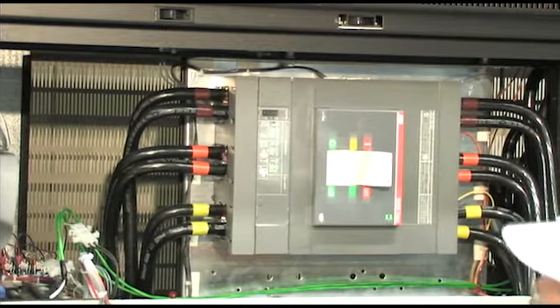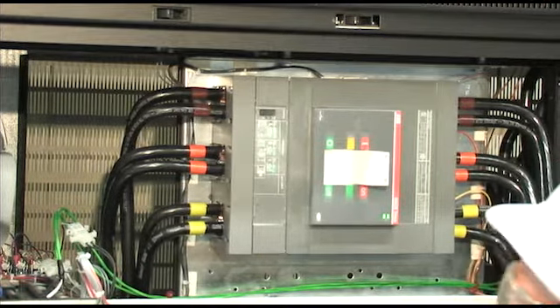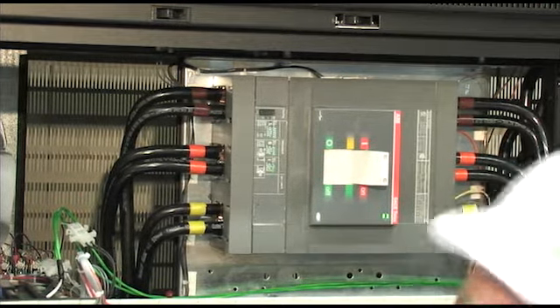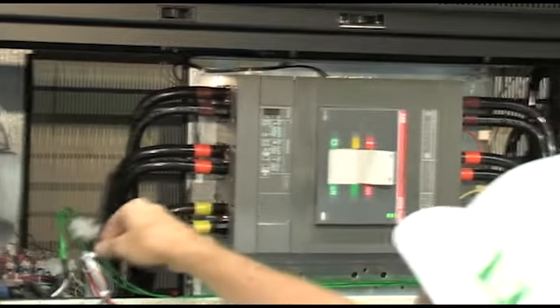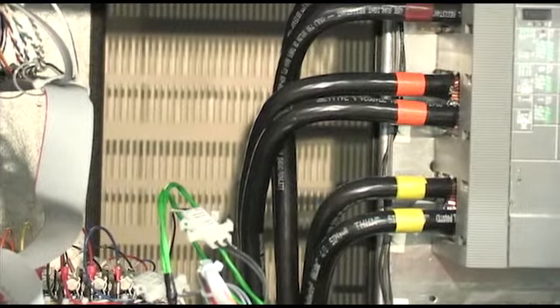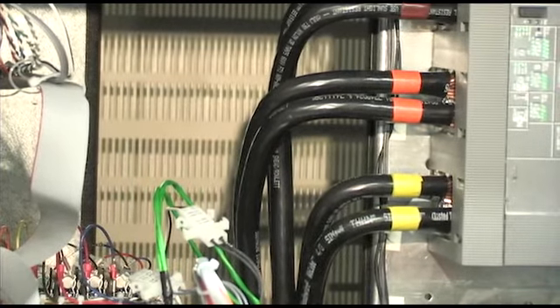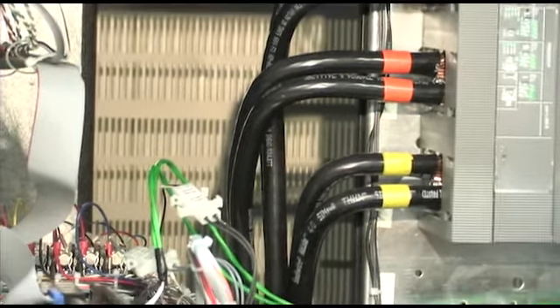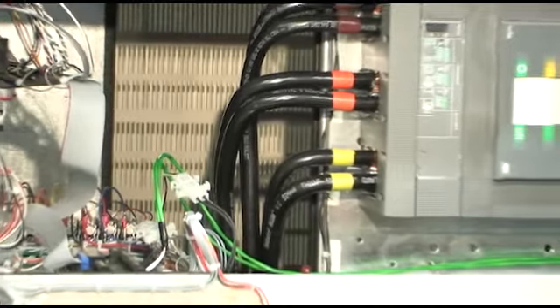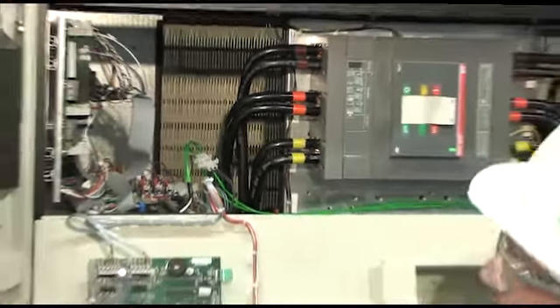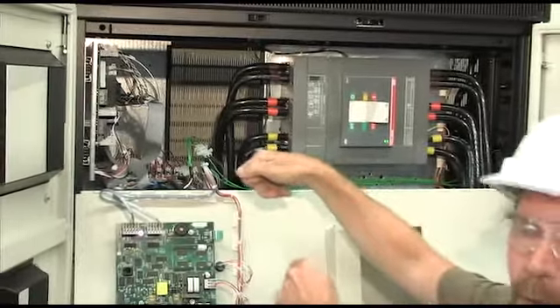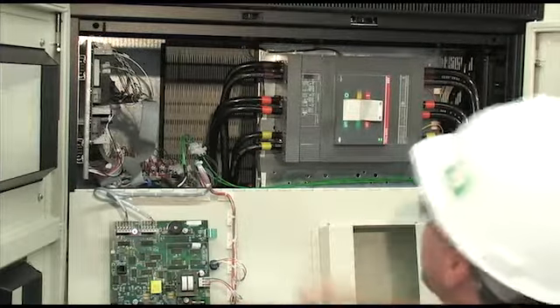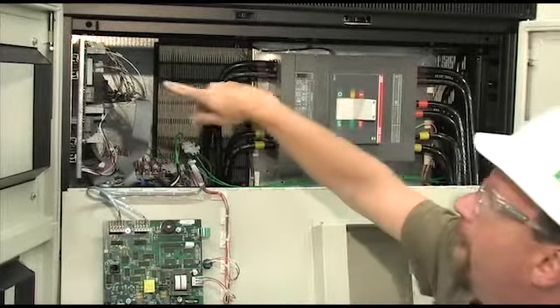And in this case, if for any reason anybody came in here to repair something, or for any other reason, this connector right here is the connector to the shunt trip to this breaker. If I was to come in and repair something, I would pull that shunt trip so that I could work on the machine without some remote chance of an incidental tripping of that breaker, which can be very, very bad. After I'm done, I'll check to see if there's voltage there if you want to be scientific about it, and then replug it in.